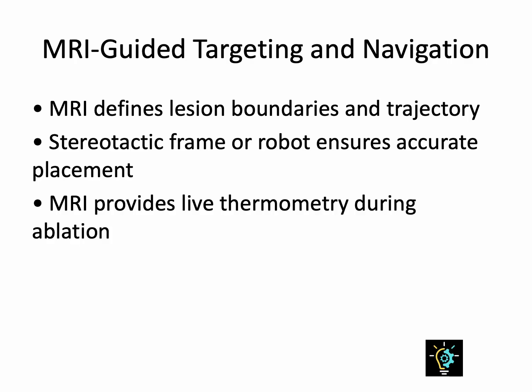MRI guidance transforms LiTT from a manual ablation to a data-driven procedure. Engineers design software that integrates MRI datasets with navigation coordinates, allowing precise targeting of deep brain structures. A stereotactic frame or robotic arm positions the laser probe with sub-millimeter accuracy. During ablation, MRI thermometry tracks heat diffusion by measuring T1 weighted signal changes. This real-time monitoring lets clinicians adjust laser power or duration dynamically. For engineers, the synchronization between the MRI system, workstation, and laser console is critical. Timing mismatches can lead to inaccurate thermal estimates or safety risks.